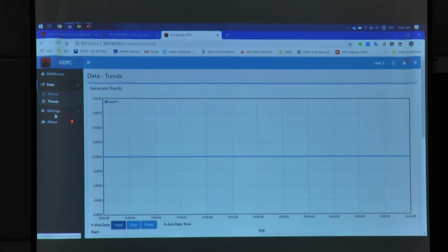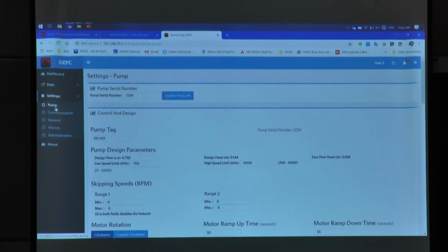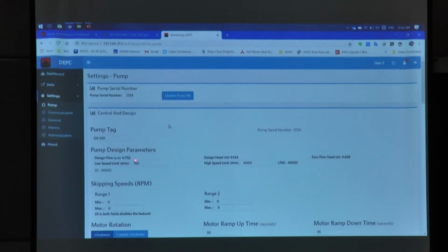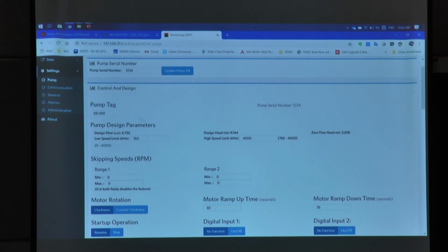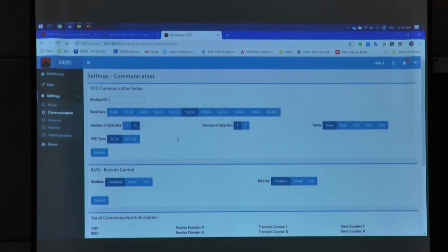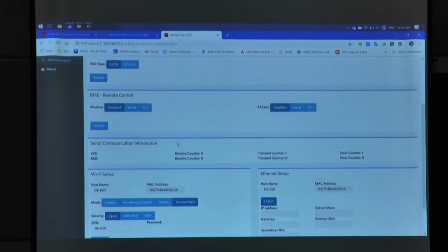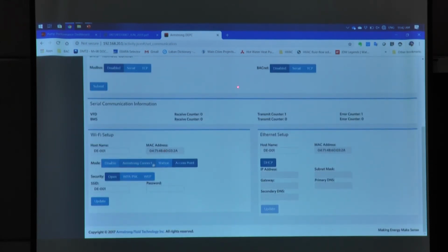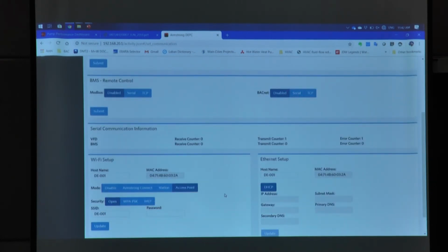And click the settings, the below pumps. You can set up the pump parameters through the settings, such as the pump tag, and also the limit for the low speed and the high speed. And also the communication parameters can be set up via this browser, such as the Modbus ID, the baud rate, and also the BMS protocols can be selected as standard. For Modbus, it is the serial or the TCP/IP, and also BACnet is available for the serial and the TCP/IP.